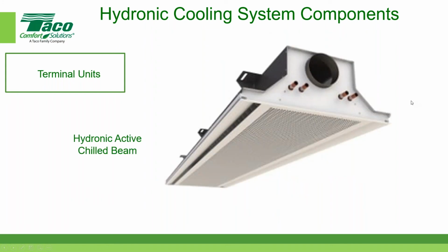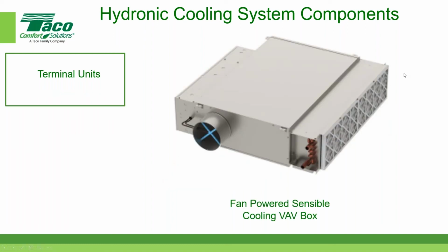You can also use hydronic active chill beams. Chill beams, in this case, it's a four pipe, which is both hot water and chilled water, or you can get them as two pipe, in which case they would be just chilled water, and you'd have to have a changeover system if you wanted to circulate hot water through them. So that's another terminal device.